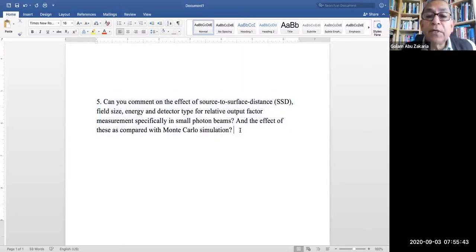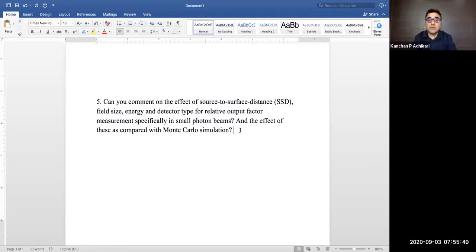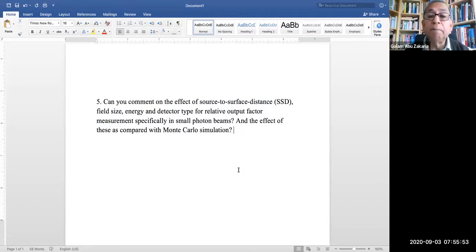Can we comment on the effect of source to surface distance, field size? Yeah. Actually, this is for the standard dosimetry. When you have other fields, there is a correction factor. You use this correction factor.